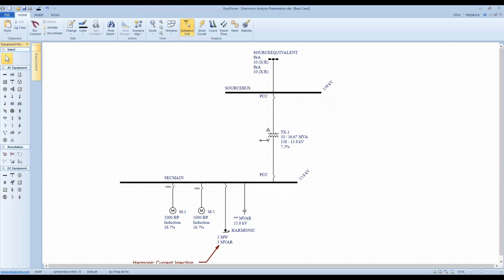Next question's from Alexander Novoa. In a normal 6-pulse drive, what are the phase displacement or angles for the 5th, 7th, 11th, and 13th current harmonics? What happens to those angles if we feed the drive with a delta-delta and a delta-Y transformer? Will those resultant angles for those current harmonics be on the high side of the transformer?